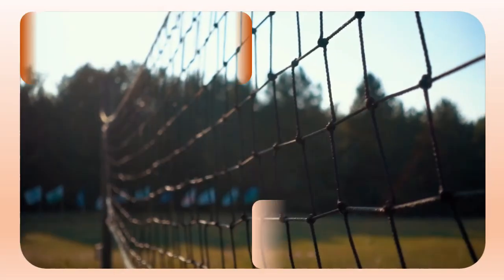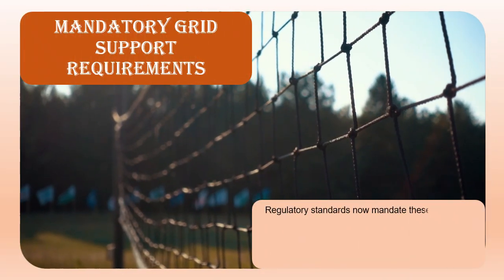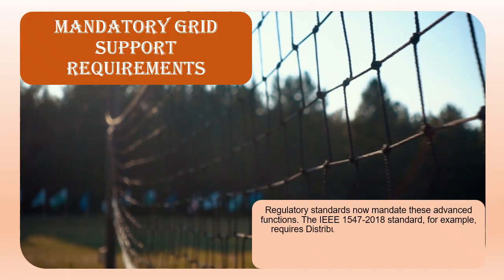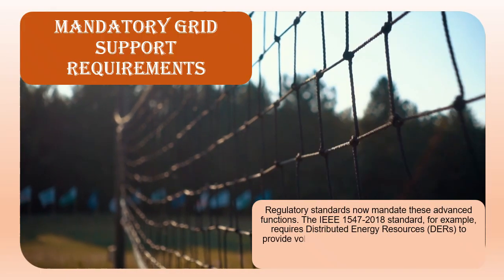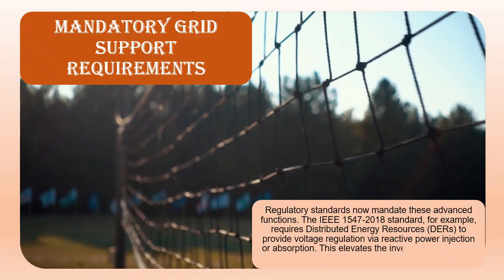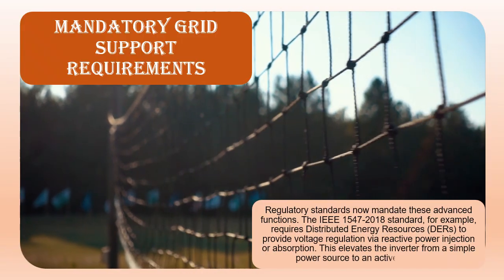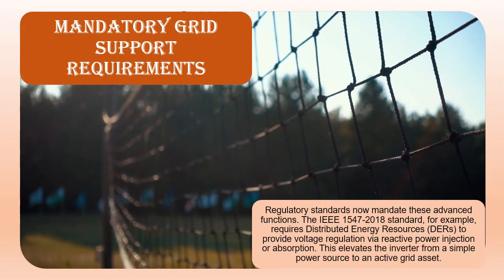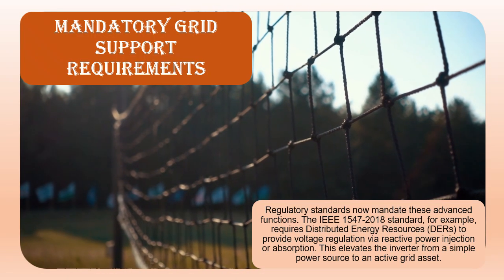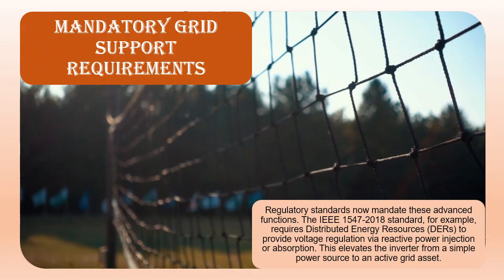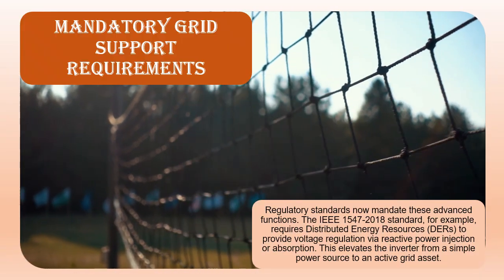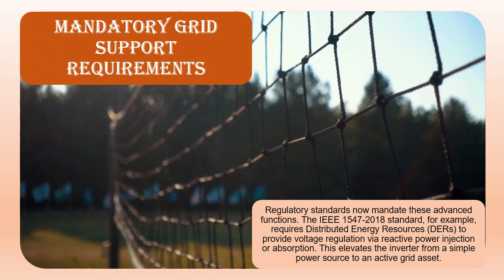Mandatory grid support requirements. Regulatory standards now mandate these advanced functions. The IEEE 1547/2018 standard, for example, requires distributed energy resources, DERs, to provide voltage regulation via reactive power injection or absorption. This elevates the inverter from a simple power source to an active grid asset.